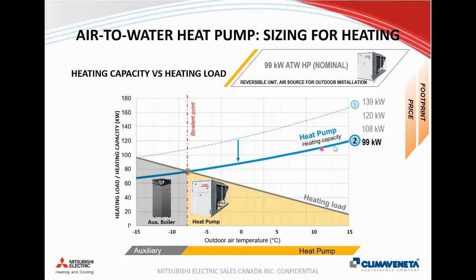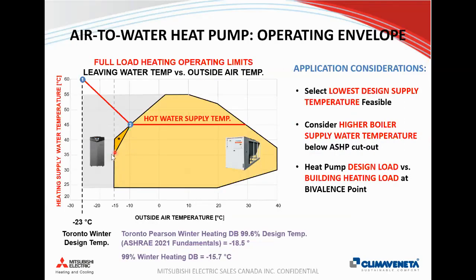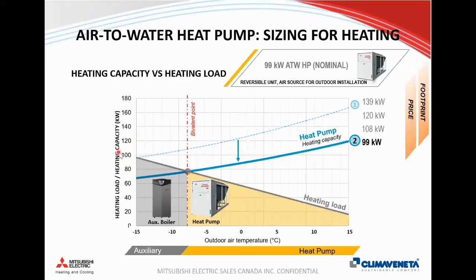The blue line here is showing us the heat pump's heating capacity. You'll see at warmer temperatures, this is where we have lots of capacity. So this line up here, number one, if we wanted to select a 140 kilowatt unit, that would allow us to meet our design down to about minus 15, assuming that we're working with a 35 degrees supply temperature. However, this example is showing a bivalence point, which just means you're switching between two different sources, the heat pump and the boiler, at about minus 7.